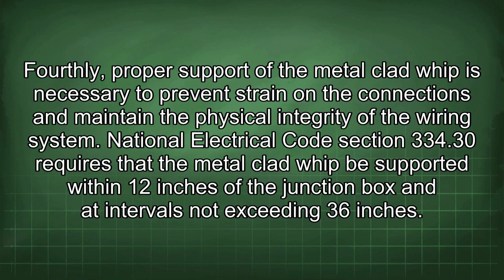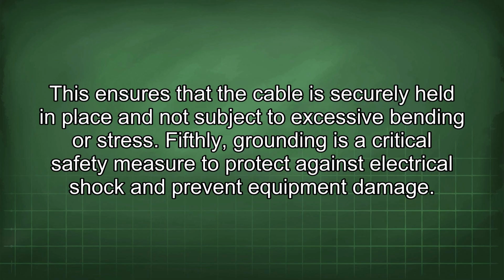Fourthly, proper support of the metal-clad whip is necessary to prevent strain on the connections and maintain the physical integrity of the wiring system. National Electrical Code Section 334.30 requires that the metal-clad whip be supported within 12 inches of the junction box and at intervals not exceeding 36 inches. This ensures that the cable is securely held in place and not subject to excessive bending or stress.